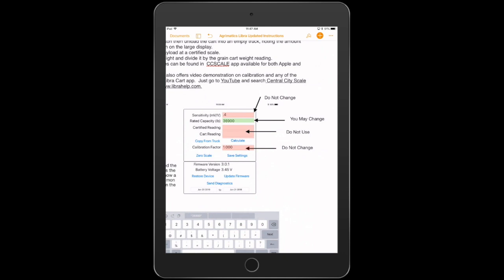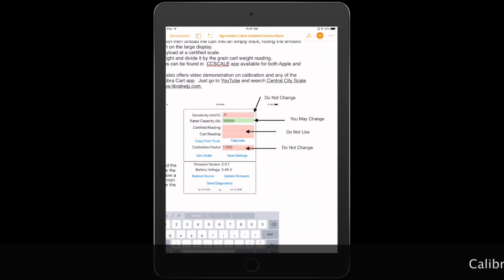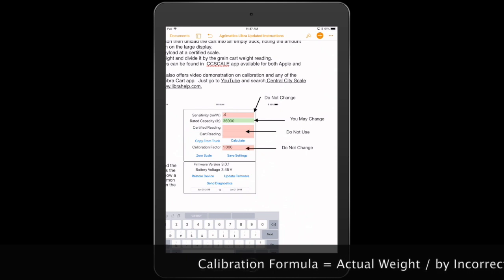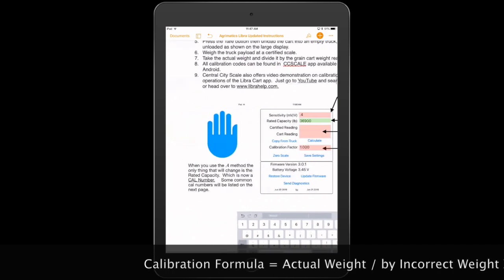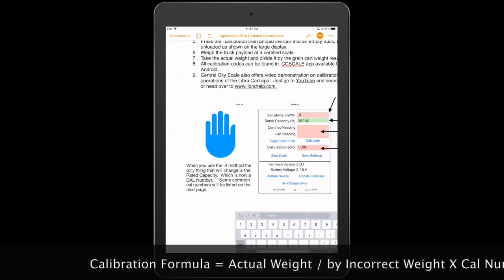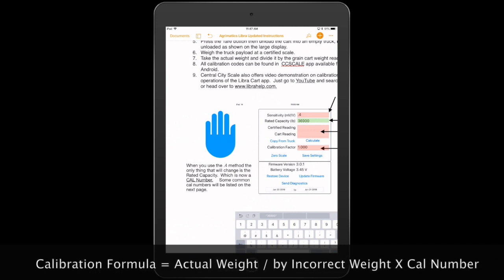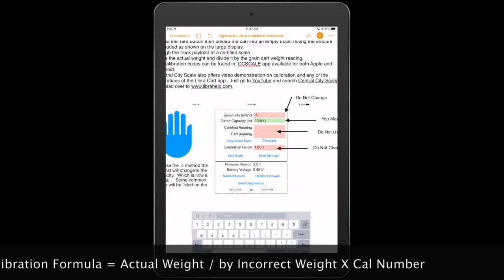So the 0.4 sensitivity, everything in red will remain the same, and then you can use the 0.4 method. So the 0.4 does not change for the sensitivity. The rated capacity is a cal number, remember, so it's green. You may change that. The certified reading and the cart reading, in this method, you can, but I probably wouldn't, because the only number that we really need to change is that 36,900. And then the cal factor, leave that at 1.000. And then after you go through and adjust that 36,900, just press Save Settings. And then I kind of explain that over here. When you use the 0.4 method, the only thing that will change is the rated capacity, which is now a cal number. Some common cal numbers will be listed on the next page.